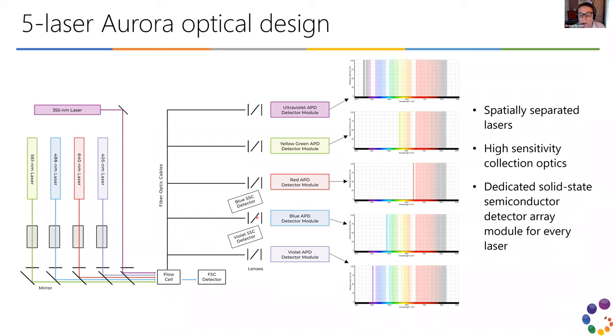We have two different side scatters. Conventionally, side scatter is measured off the blue laser. We added a violet side scatter, which has been shown to give better resolution of small particles. We have both available — blue so you can compare to other instruments, and violet because it gives better resolution. There's also a trick where combining these two types of scatter lets you find red blood cells, because hemoglobin scatters different wavelengths differently than white blood cells.